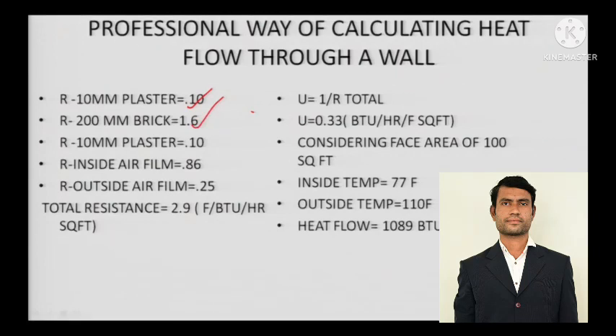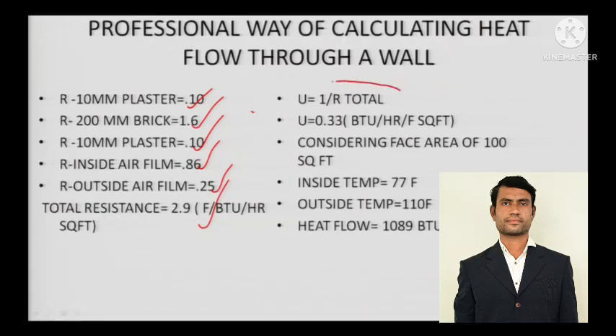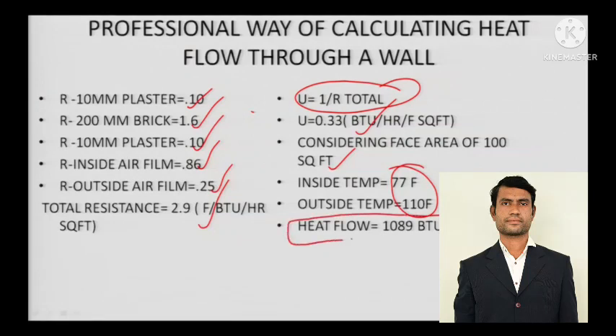So: 10 mm inside plaster, 200 mm brick wall, 10 mm outside plaster, inside air, outside air — all resistances have been calculated. Then U equals 1 divided by R. Considering a face area of 100 square feet, inside temperature of 77°F and outside temperature of 110°F, the heat flow across the wall that needs to be removed by the air conditioning unit is 1089 BTU per hour.